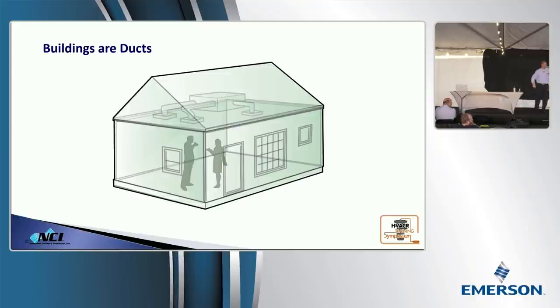That's an excellent point. For those of you who do kitchens, restaurants, and stuff, that makeup air is coming right down on the kitchen. And then I'm from Arizona, so in the winter time, it gets cold, you know, 60 degrees, and they'll turn off the makeup air. It starts pulling makeup air from bathroom vents. So the question was made in Arizona when it's in their winter, which all of us, it's hard for us to sympathize with you, Jake. Their winter that they have in Arizona, you know, when it gets warmer, they start to shut off the makeup air. And that makeup air is coming in from somewhere. You guys make some excellent points, because that's air doing what it does. So fantastic points. Thank you for that. Your winter's awesome, man. I love your winter in Phoenix. Yeah, so it's awesome.